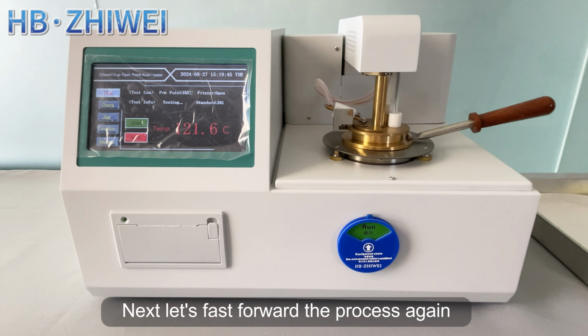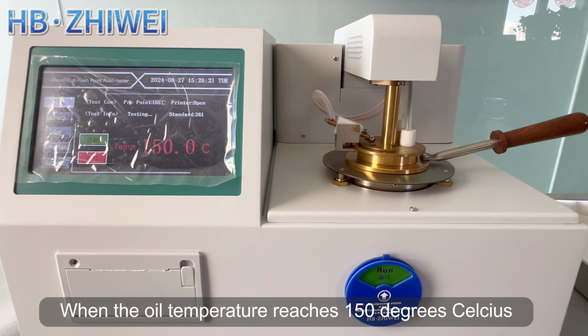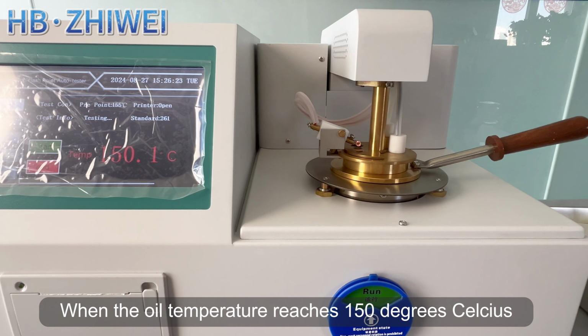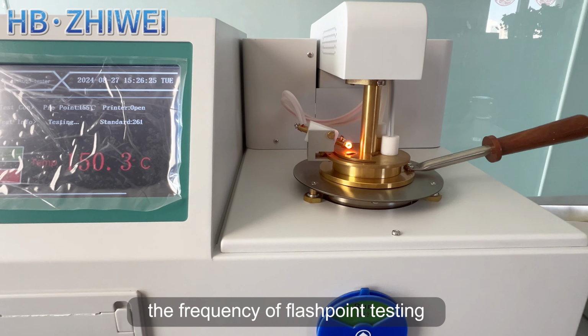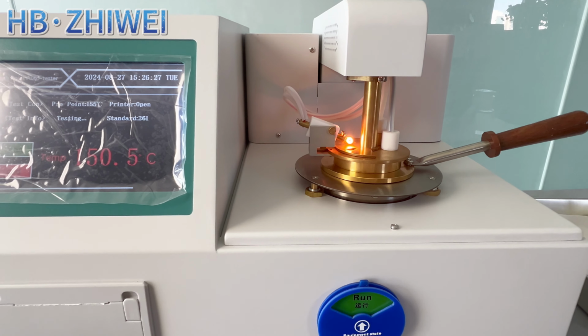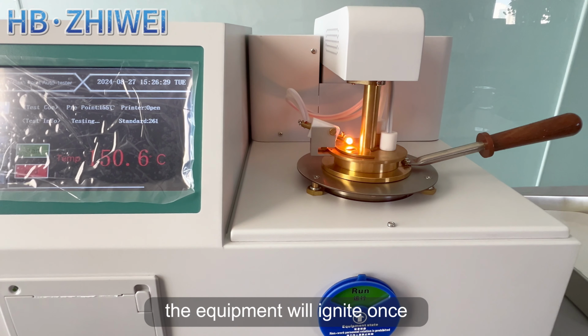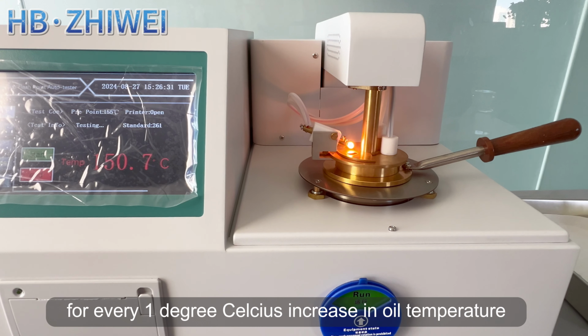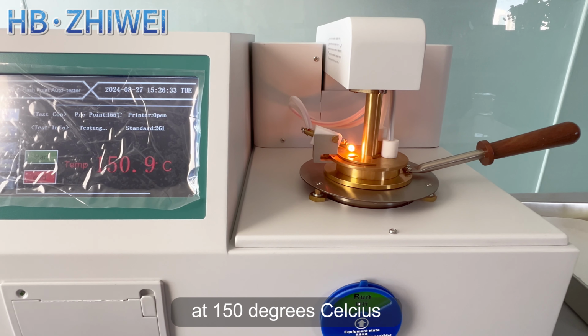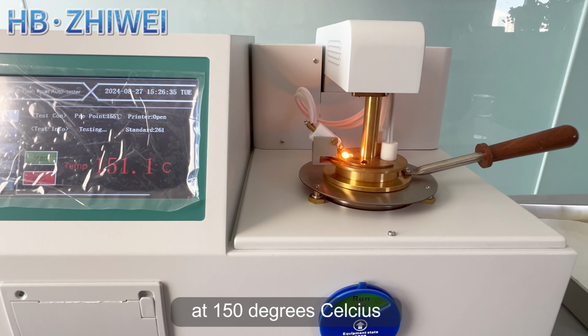Next, let's fast forward the process again. When the oil temperature reaches 150 degrees Celsius, the equipment will increase the frequency of flashpoint testing. Under the standard we chose, the equipment will ignite once for every 1 degree Celsius increase in oil temperature at 150 degrees Celsius.